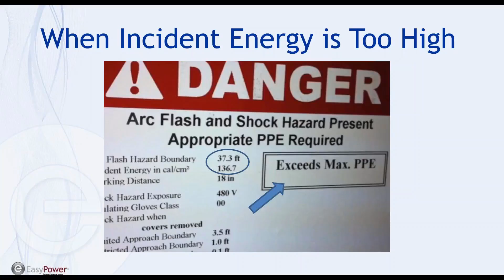Another situation is when you need to de-energize or energize. When we talk to customers, or at a trade show, we'll ask potential customers about what kind of policies they have, and they say we don't work on anything energized, we always de-energize for any kind of maintenance. I have to question where upstream you de-energize and re-energize, because at some point there's going to be switching taking place, and if you don't have a mimic panel or other solution in place, our tools could be of use - throwing an MCC handle, or tripping or closing a breaker, and then racking it for maintenance.